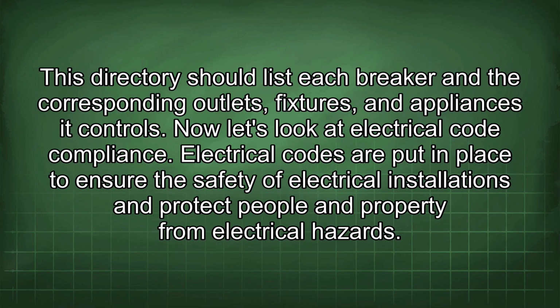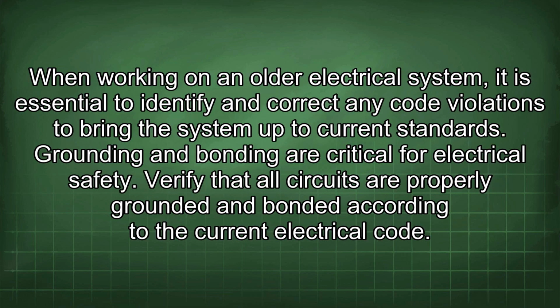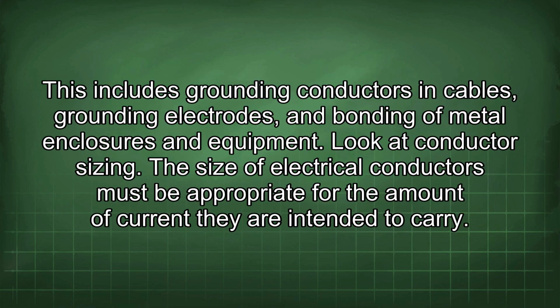Now let's look at electrical code compliance. Electrical codes are put in place to ensure the safety of electrical installations and protect people and property from electrical hazards. When working on an older electrical system, it is essential to identify and correct any code violations to bring the system up to current standards. Grounding and bonding are critical for electrical safety. Verify that all circuits are properly grounded and bonded according to the current electrical code. This includes grounding conductors in cables, grounding electrodes, and bonding of metal enclosures and equipment.